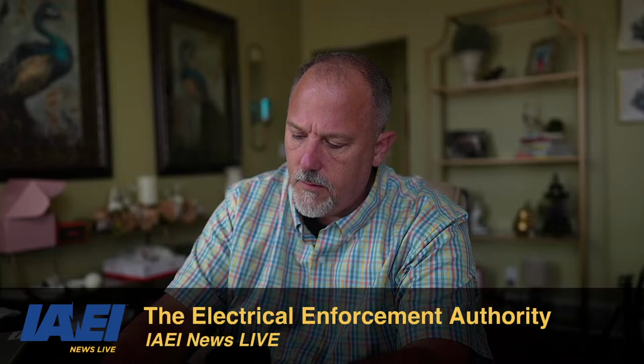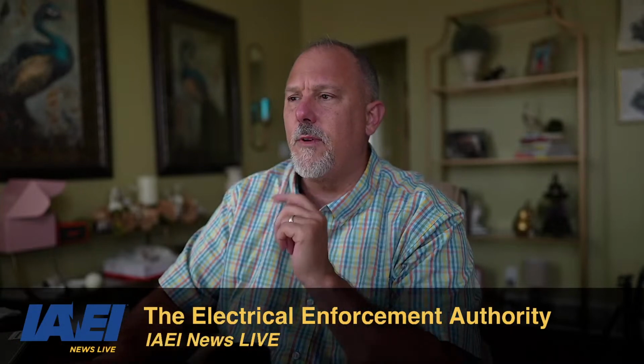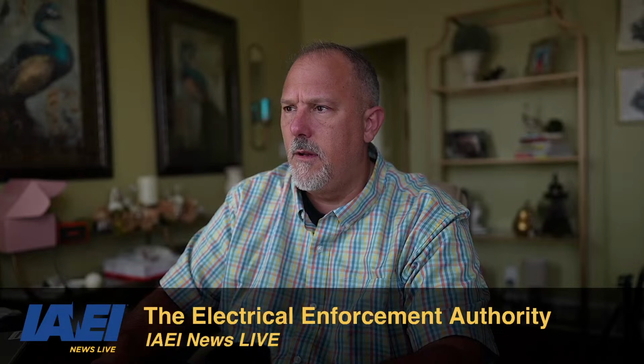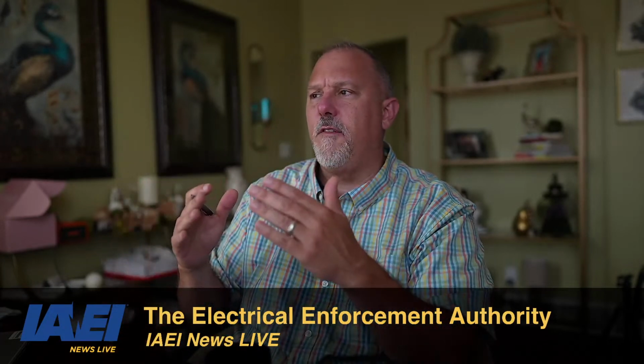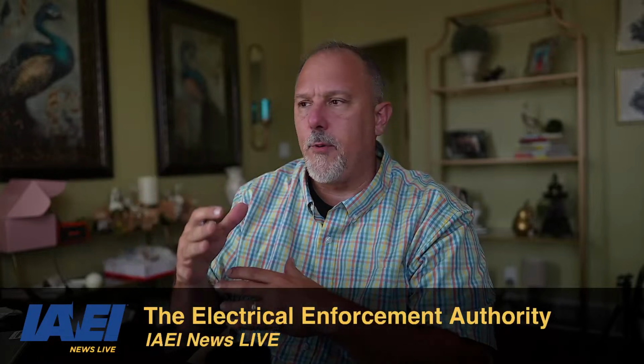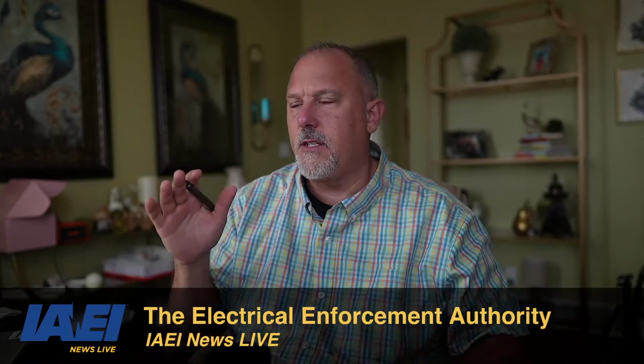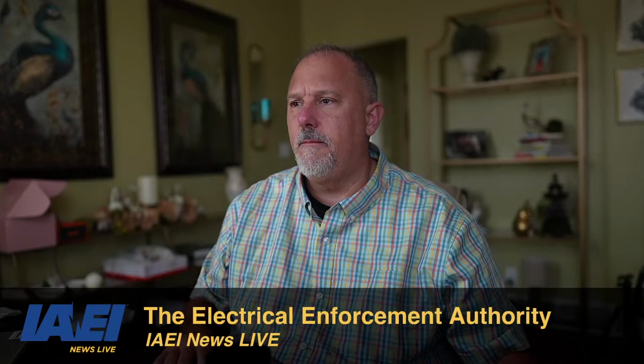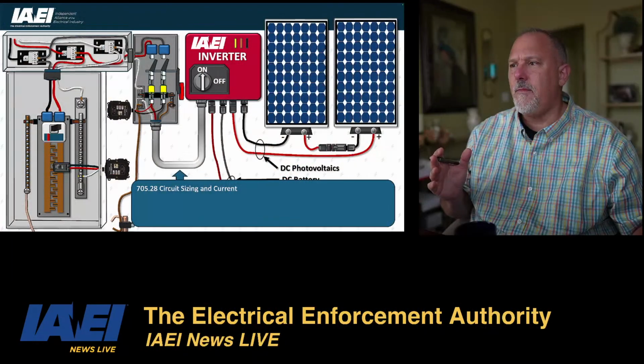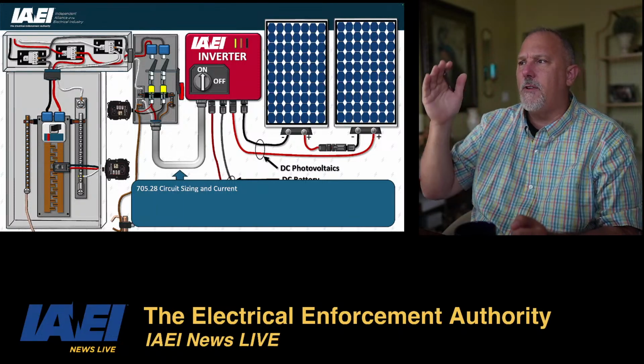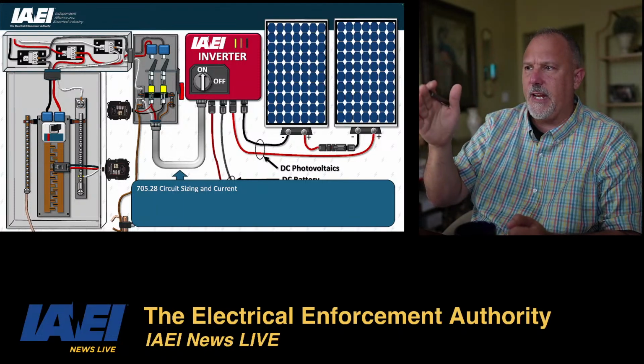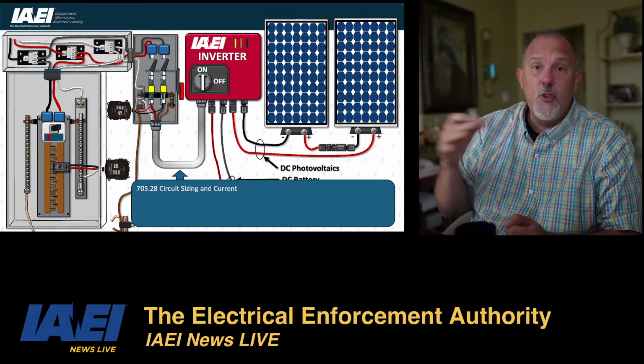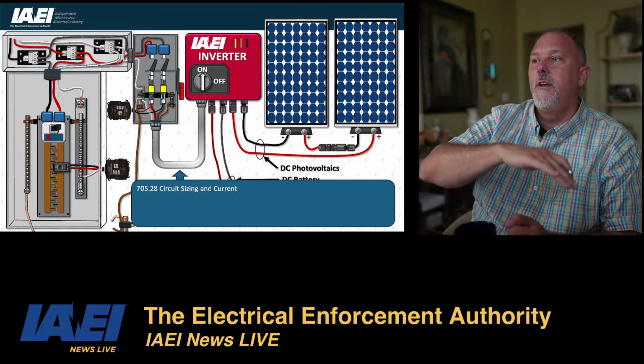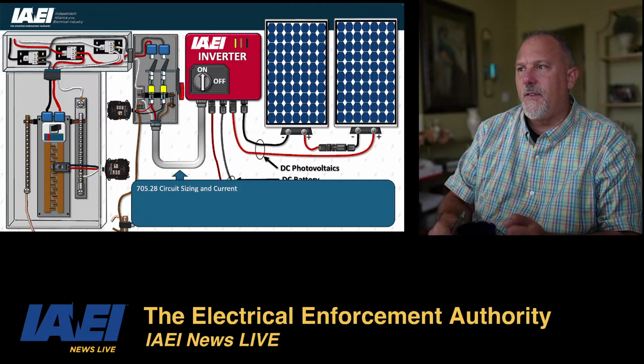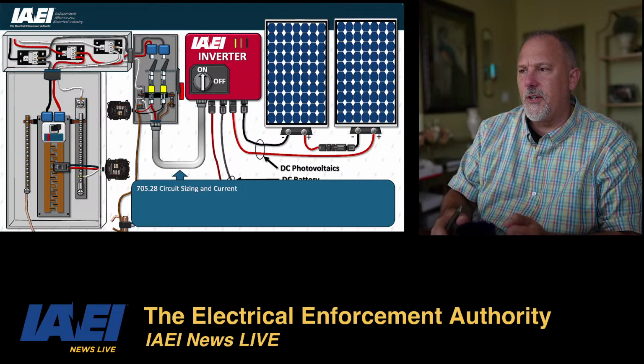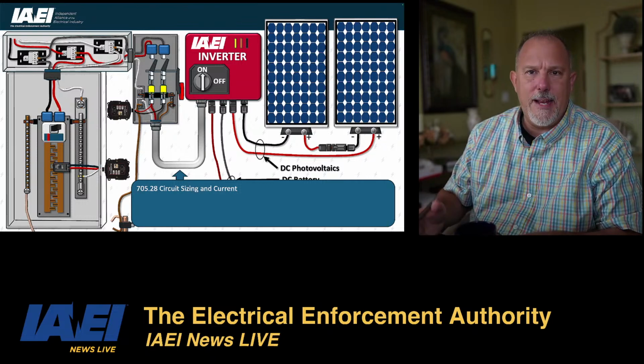So, power flow. I don't show the power flow during normal operation on these slides because I should, but I don't. But that disconnect, the power is going to be going from the inverter through the disconnect during normal operations. But during faults, I have the fault current flowing from line to load. So you have to make sure that the equipment can handle reverse power feed.